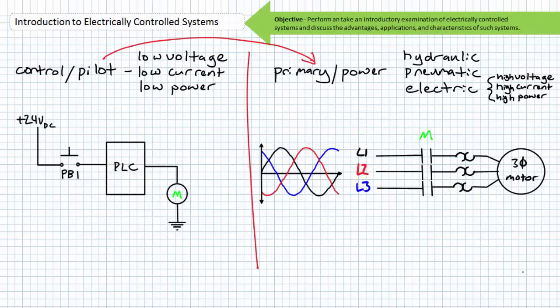How different is this application from an electrically controlled motor? Consider an industrial motor that requires 480 volts three-phase AC to operate, however, does so only at the request of a programmable logic controller, a PLC, basically a form of ruggedized computer that operates at 24 volts DC. The principal point of interaction between the control or pilot and the power or primary signals for this type of system is a contactor. A contactor is akin to a solenoid-operated directional control valve in an electrically controlled hydraulic system.